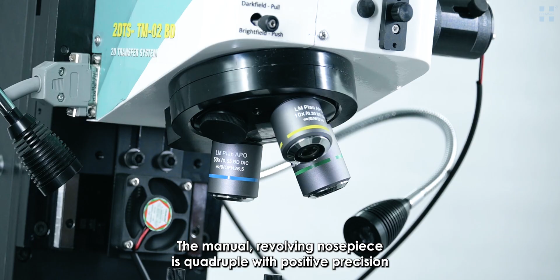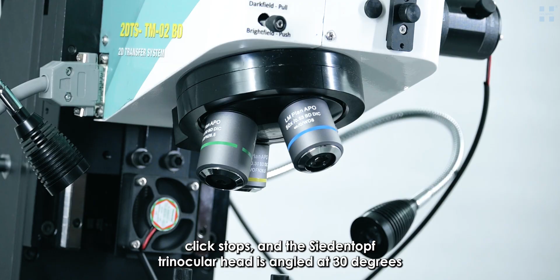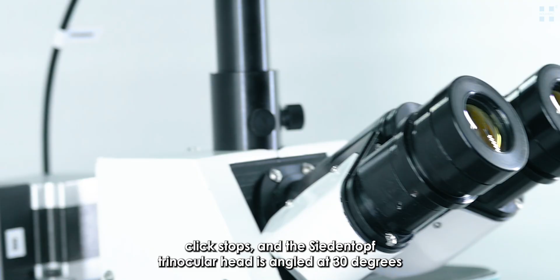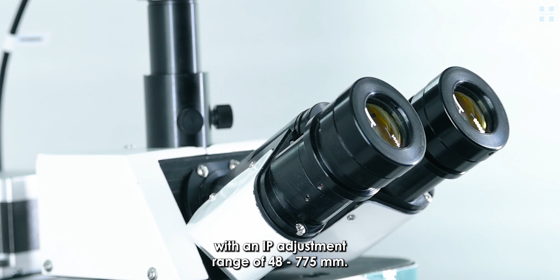The manual, revolving nosepiece is quadruple with positive precision click stops, and the Siedentopf trinocular head is angled at 30 degrees with an interpupillary adjustment range of 48 to 75 mm.